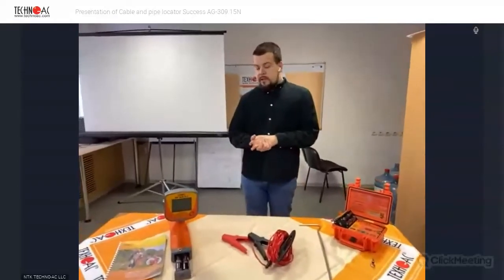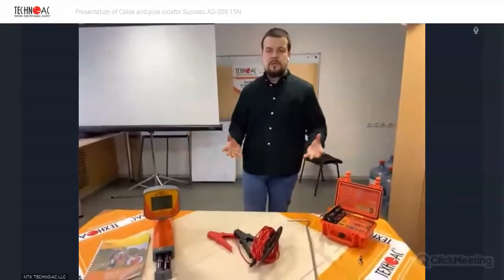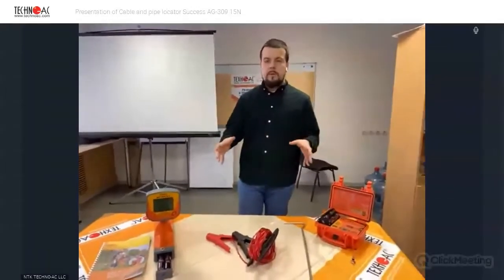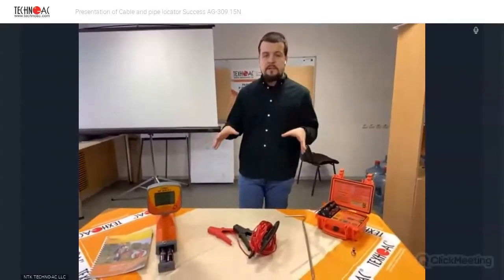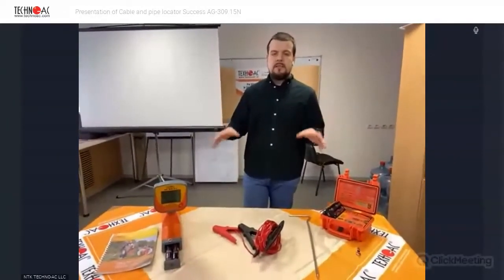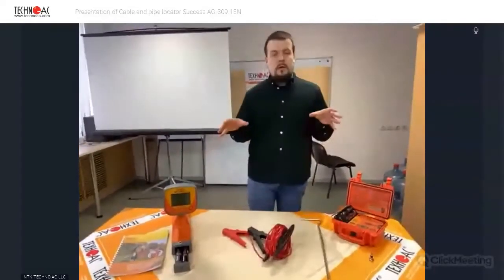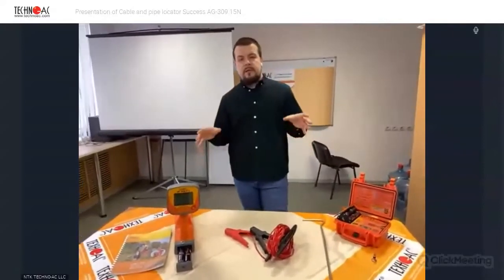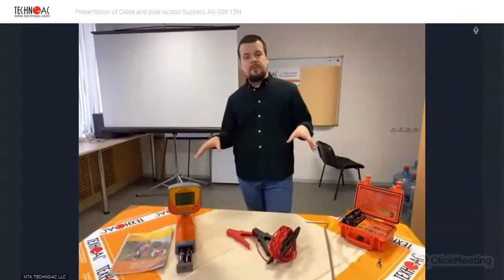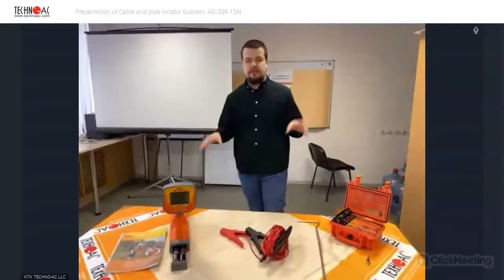I would like to say that for all locations, for all the utilities which I have given you before, the limitation for the location is the following. The device recognizes any metal utility underground at depth up to 10 meters. This is the limitation when the locator can measure the depth. But recognition depth is much deeper. The recognition depth for this device is 30 meters.